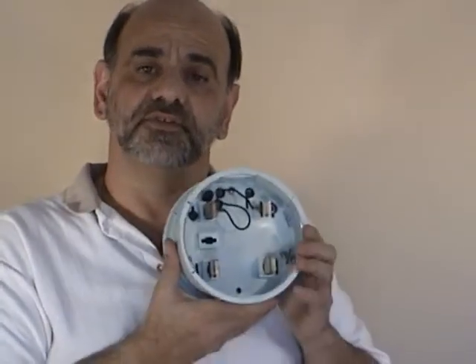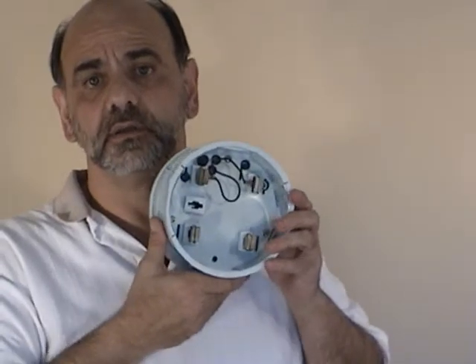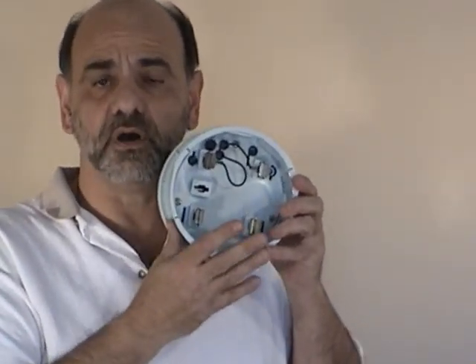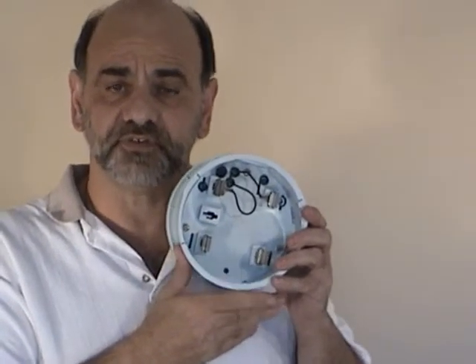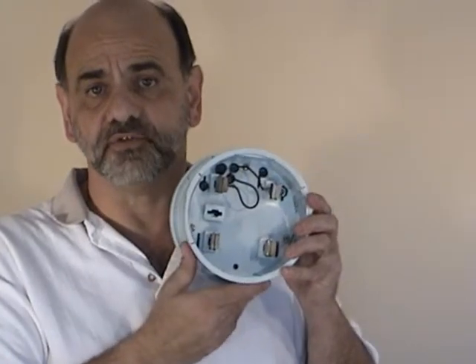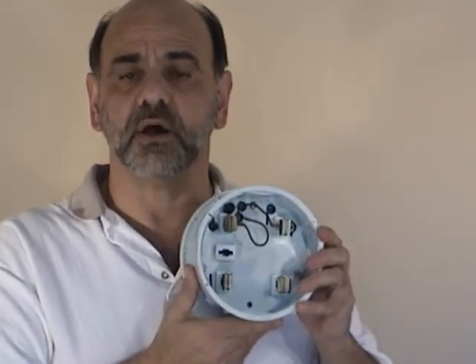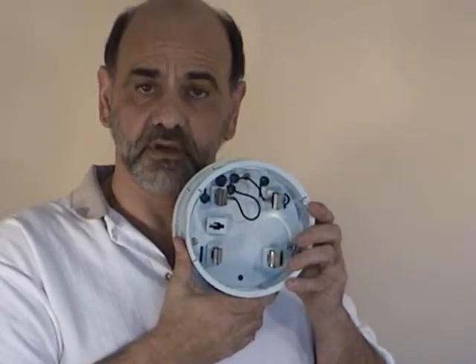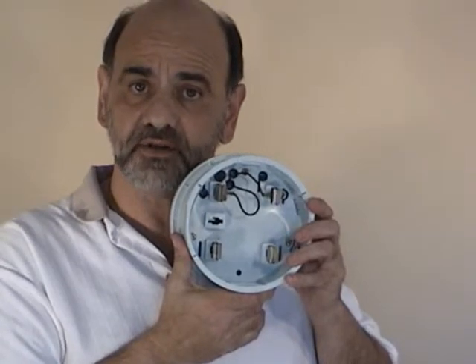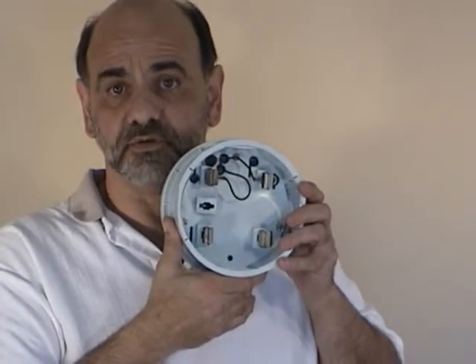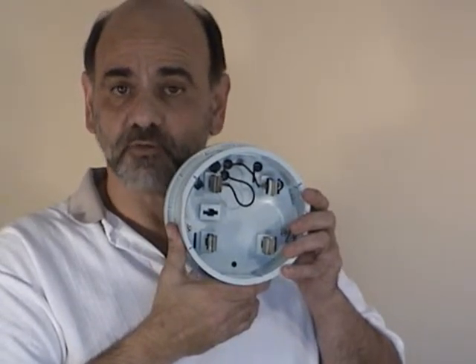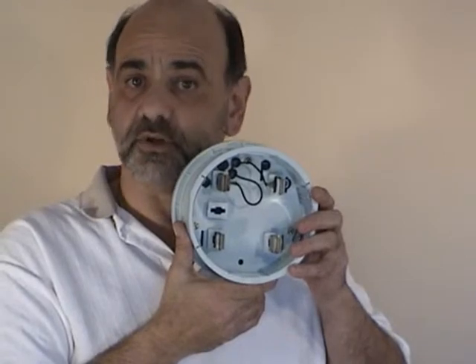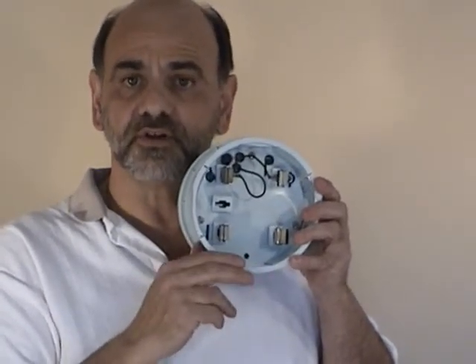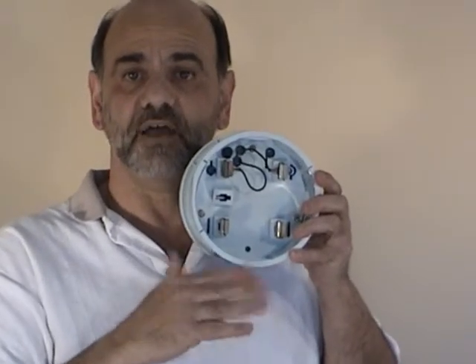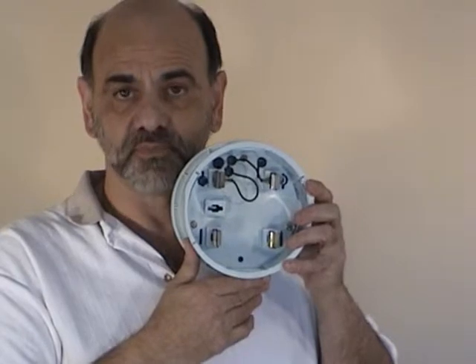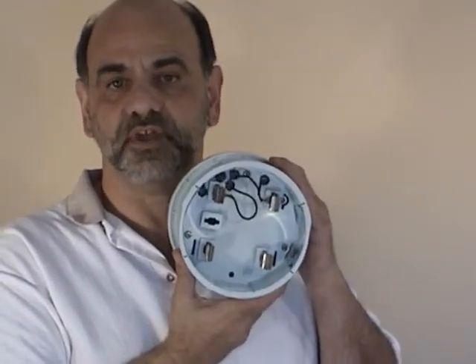The unit comes standard with a 7-day recording time frame embedded into the firmware of the unit. We also have 2 set points set at 5% above and below the nominal 120. This means that the set points that we use are 126 and 114. This, from surveying most of the power companies in the United States, is what most of you are interested in. Those set points can be changed with the software program called PM Screen, which we'll be showing you a little bit later. The standard is 126 volts and 114 volts, and that's 5% plus and minus above the 120 volt nominal. The 0 to 200 amps is always in place. There are no set points on the current channels.